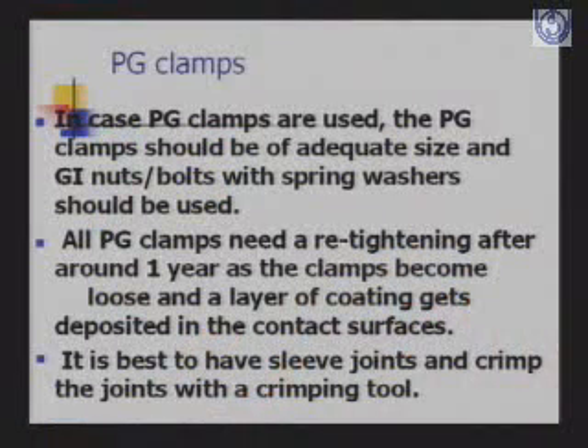Then PG clamps. In case PG clamps are used, the PG clamps should be of adequate size, and GI nuts, bolts with spring washers should be used if these are used for clamping. All PG clamps need to be retightened after around 1 year, as the clamps become loose and a layer of coating gets deposited on the contact surfaces. So you should re-examine and retighten all the PG clamps.